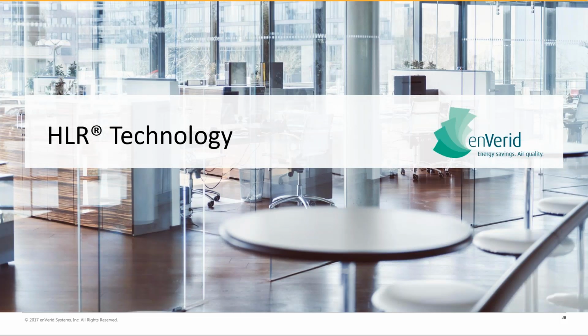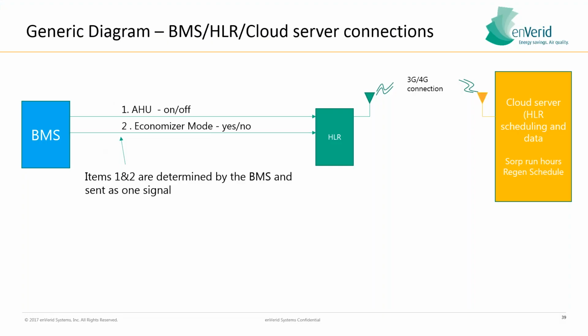Speaking about the technology just a little bit here. So I mentioned that we do have BACnet integration. Essentially, we want to be able to integrate with the air handler, determine run hours, and schedule regeneration during off hours. It's a 24/7 building. We can stagger regeneration of units during times of lower occupancy. And then also economizer mode. If the air handler and the building is in economizer mode, we will go into standby, okay? So you can still take advantage of those energy savings from economizer mode.